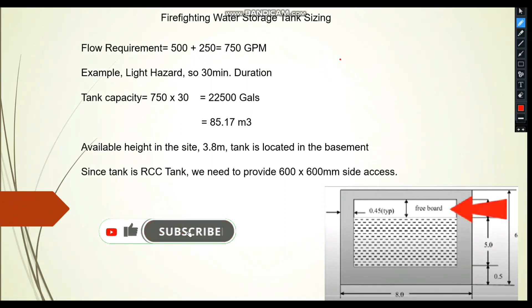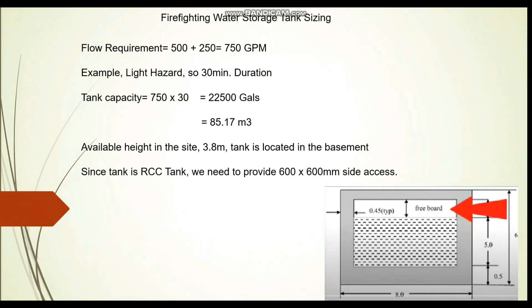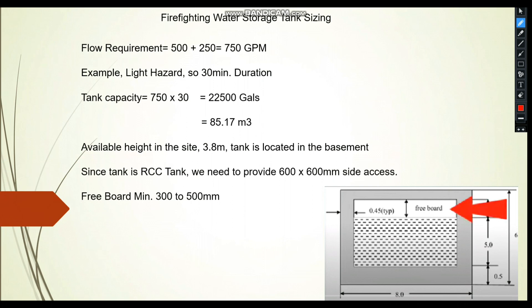Since the tank is an RCC tank, we need to provide a side access opening of 600 mm by 600 mm so that maintenance personnel can enter from outside. Some projects use 700 mm by 700 mm; in this example we use the minimum 600 by 600 mm. Additionally, we must account for freeboard — a zone kept free of water to accommodate float valves and other equipment — typically 300 to 500 mm. In this example we use 500 mm for freeboard.